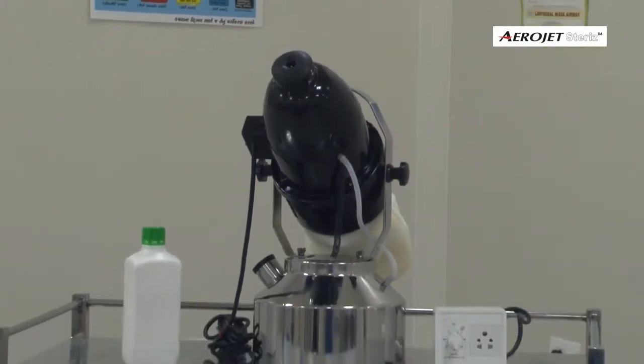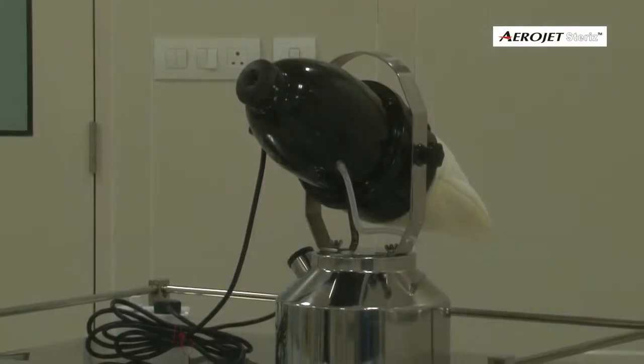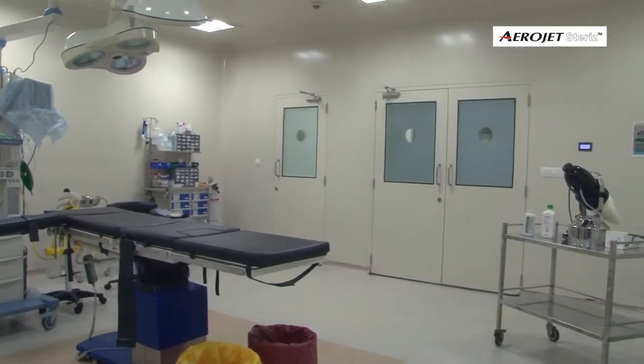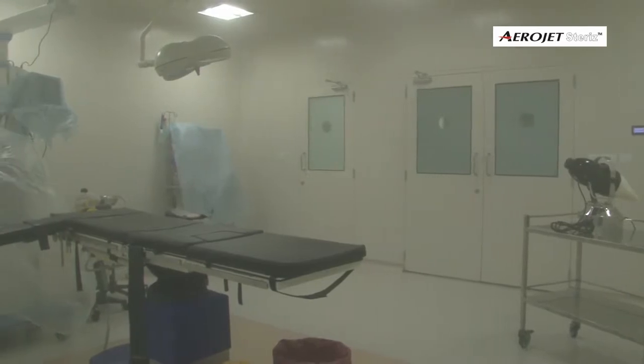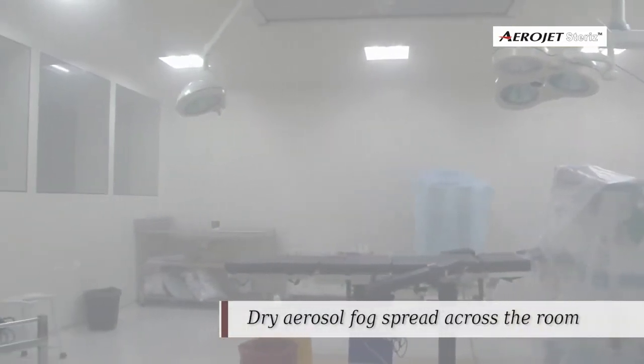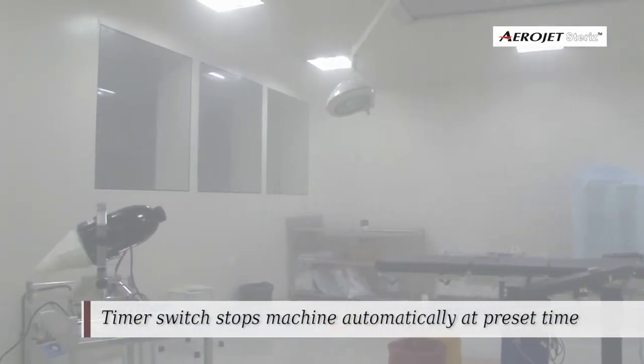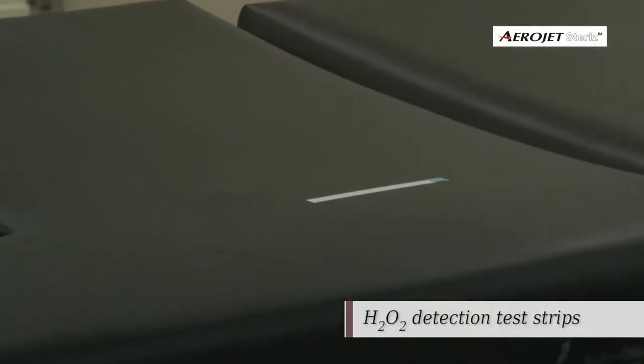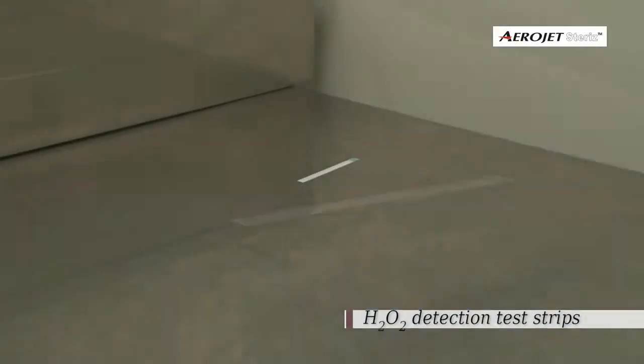We conducted a trial at GCS Medical College and Hospital on the disinfection efficacy of Aerojet Steriz Vaporizer combined with an H2O2 based fogging disinfectant. We disinfected an operation theatre space of about 4000 cubic feet. Aerojet Steriz, kept in a fixed location in one corner of the OT, was powerful enough to spread dry fog across the room. H2O2 detection test strips placed in various locations of the OT validated the uniform spread.